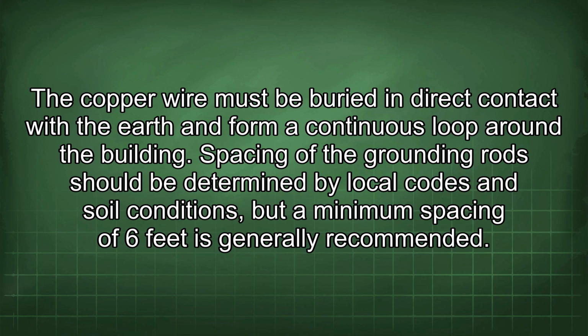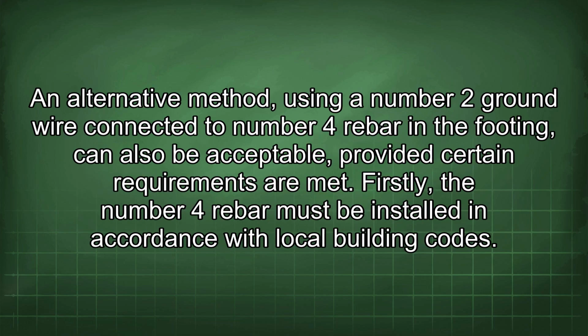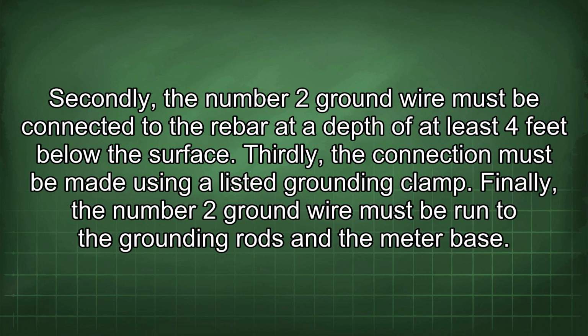feet is generally recommended. An alternative method, using a number 2 ground wire connected to number 4 rebar in the footing, can also be acceptable, provided certain requirements are met. Firstly, the number 4 rebar must be installed in accordance with local building codes. Secondly, the number 2 ground wire must be connected to the rebar at a depth of at least 4 feet below the surface. Thirdly, the connection must be made using a listed grounding clamp. Finally, the number 2 ground wire must be run to the grounding rods and the meter base.